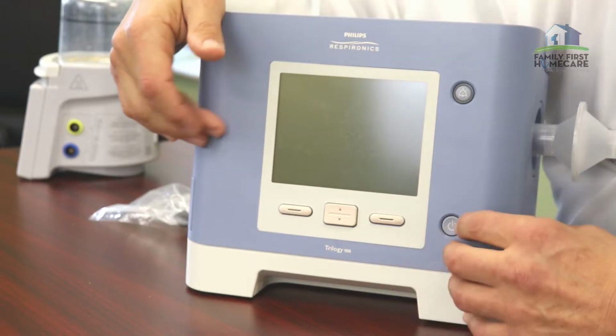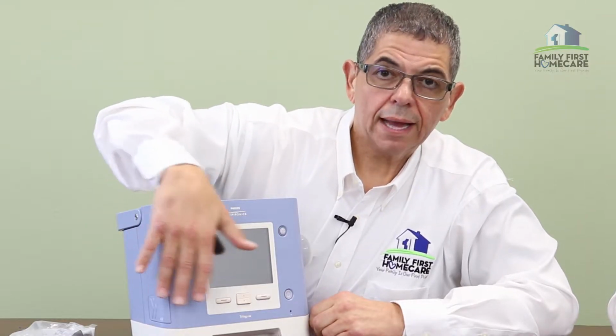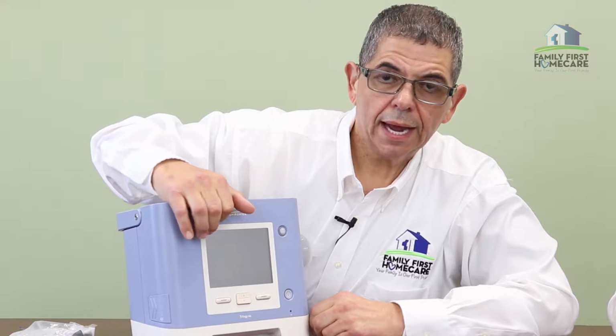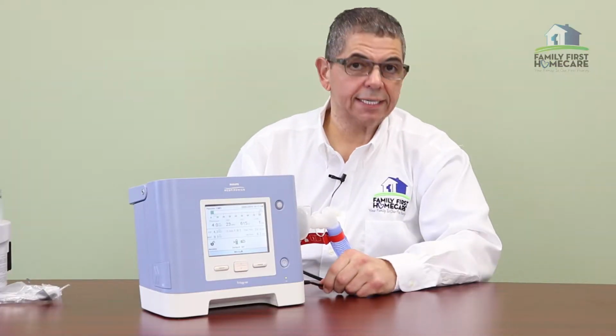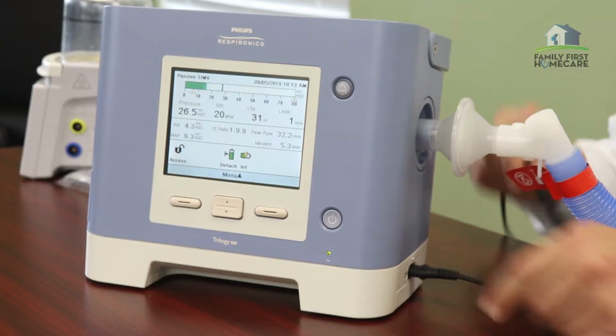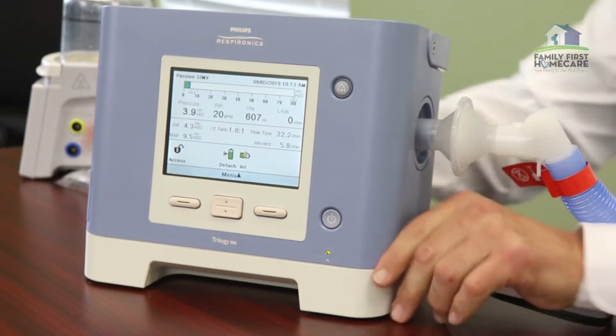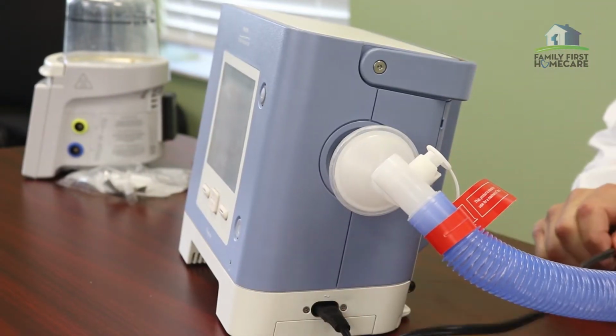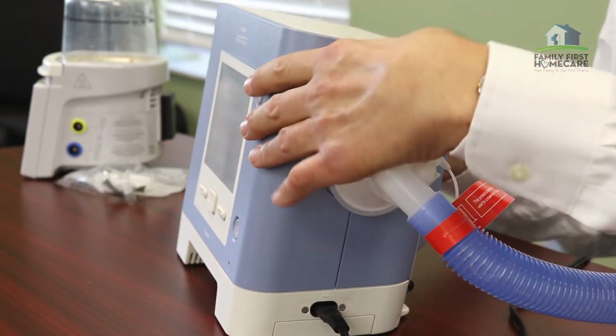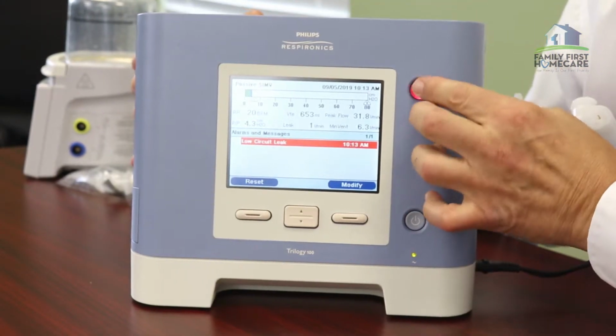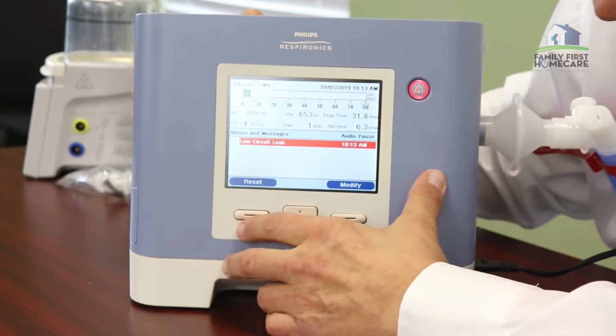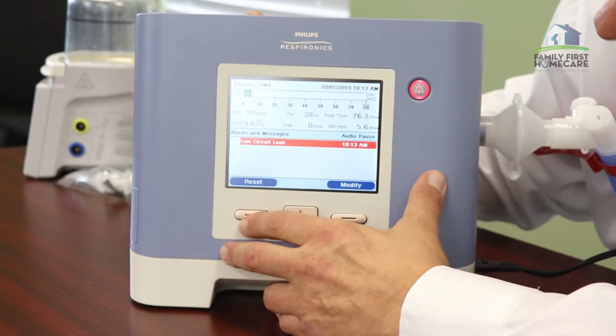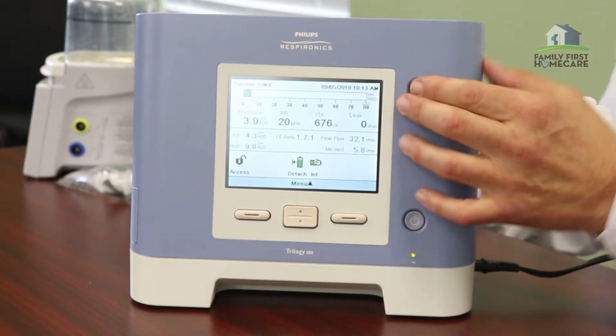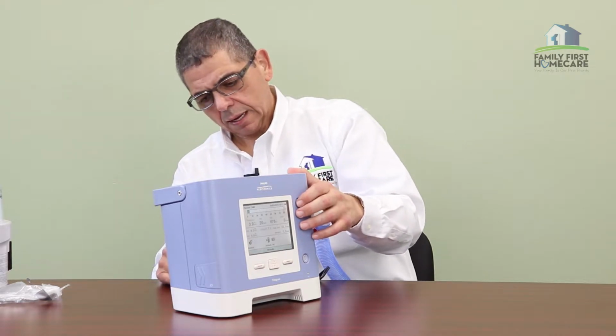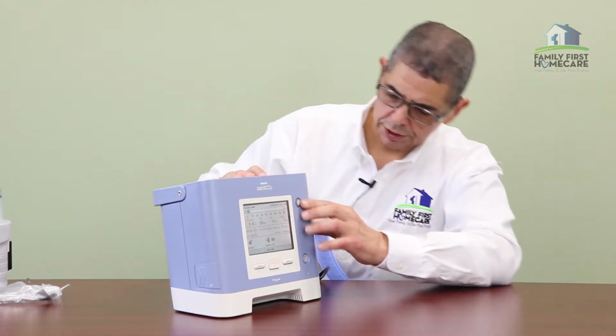You can see I'm going to turn the power on, and I'll be able to light up the screen for you and show you the controls. You'll notice this time I have it plugged into the wall. This is the only time you would use this port right here on the side, when you're plugging into the wall. The rest of it... there goes an alarm. We'll go ahead and shut that off. That was a low circuit leak. That's probably because I'm in the mode of trying to show you the ventilator. So we'll be quick to do that.